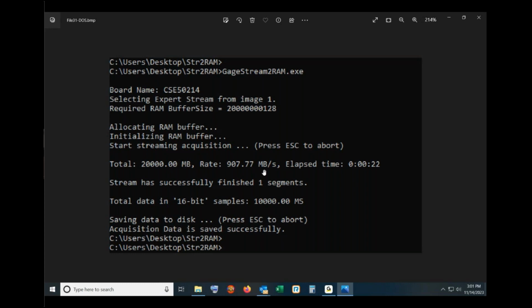So we're streaming the data onto the PCI bus and into PC RAM, but through the card's onboard memory. So if the PC RAM were, for some reason, which it never does, to get locked up for a little while, or if the PCI bus was to get locked up, which can happen, but not for very long, the card's onboard memory would accept that overflow, just as if you plugged the sink and kept the water flowing. It wouldn't overflow until the sink got filled up. Similarly, until the onboard memory got filled up, you wouldn't miss any data. And if the plug got pulled in the sink, the water that filled up the sink would drain off. Similarly, as soon as the PCI bus became unlocked, it would empty out that FIFO as long as it wasn't blocked for too long. So that analogy works quite well.